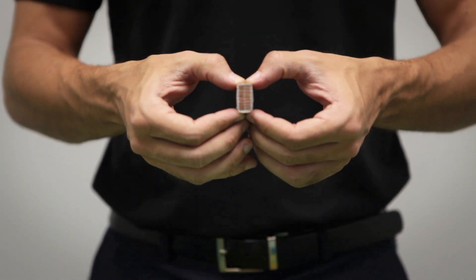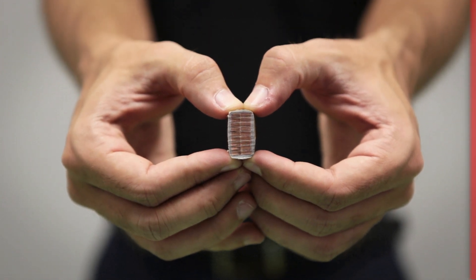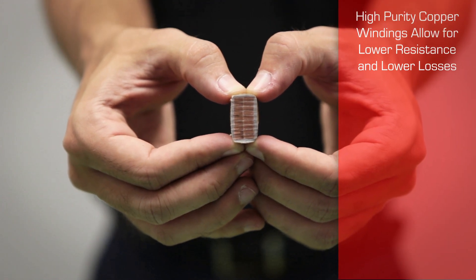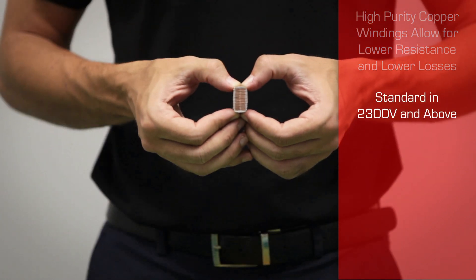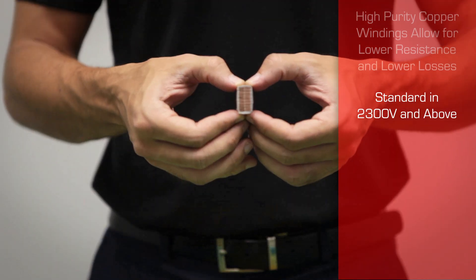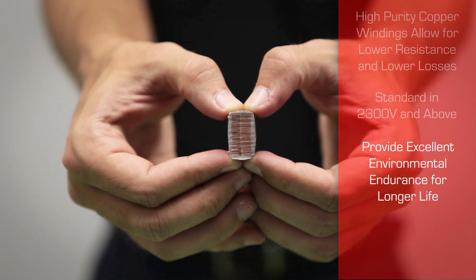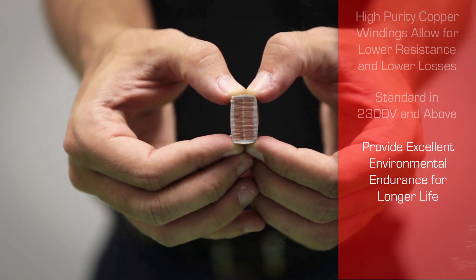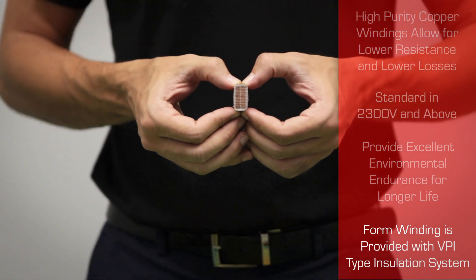The great majority of our medium voltage motors are made with form wound coils. High purity copper windings allow for lower resistance and lower losses. They are standard in 2300 volts and above and also available in some larger low voltage designs, providing excellent environmental endurance for longer life. Form winding is always provided with a VPI type insulation system.